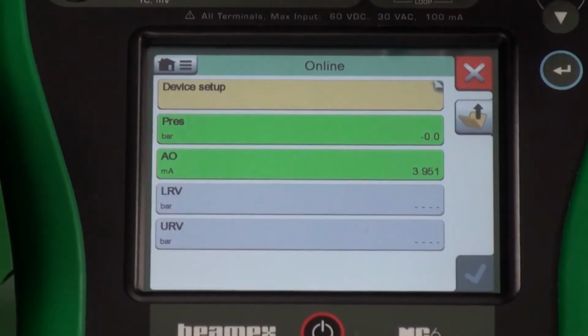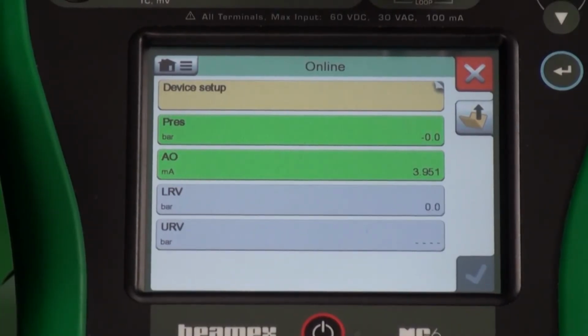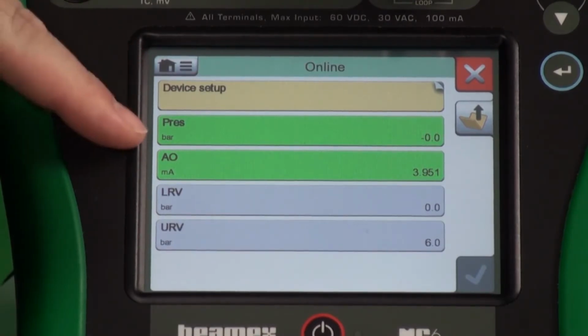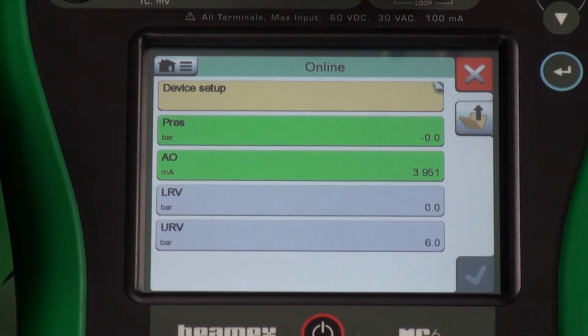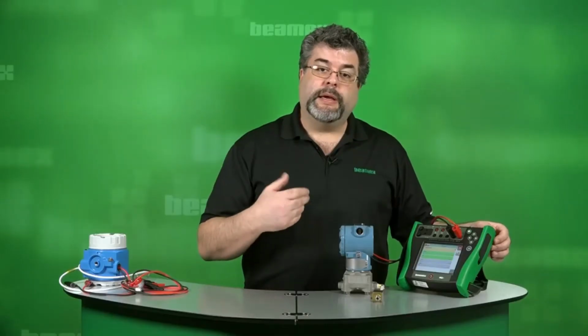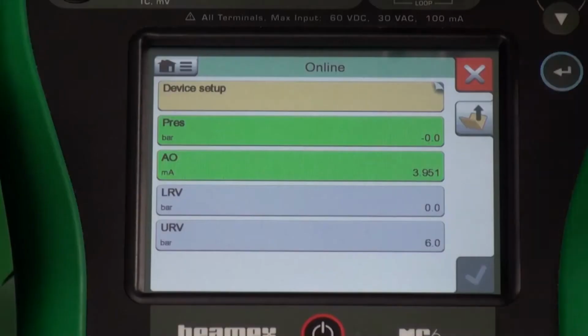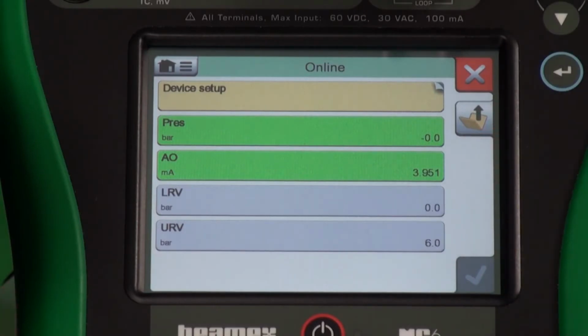Anytime you have the yellow with the little corner flap that's up, that means that there's another level underneath it. Green means that those are measurable variables. You can see our LRV and URV right here. So you can make changes. We can change the tag name. We can change how it's ranged. This has a range right now of 0 to 6 bar. We could change that value, or we could change the units.